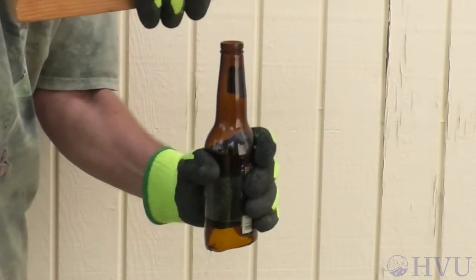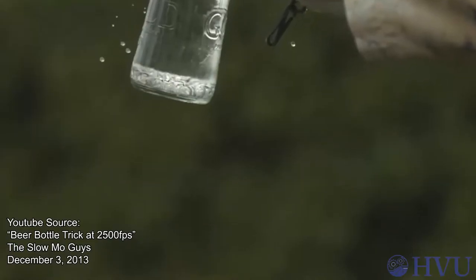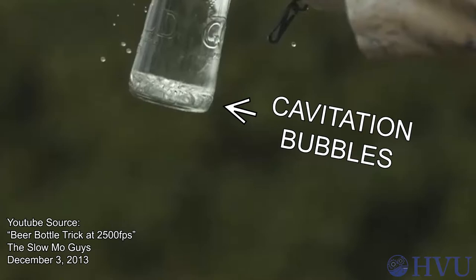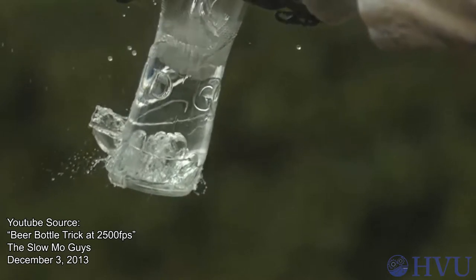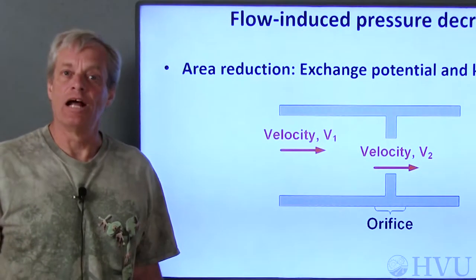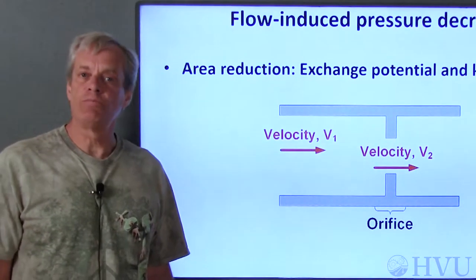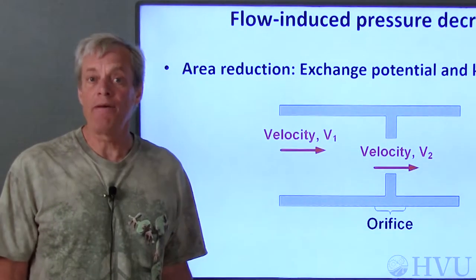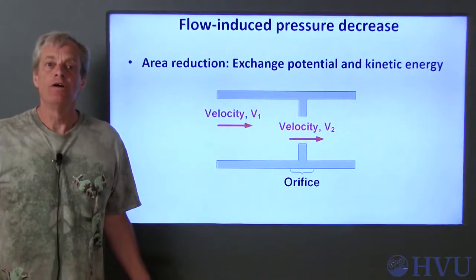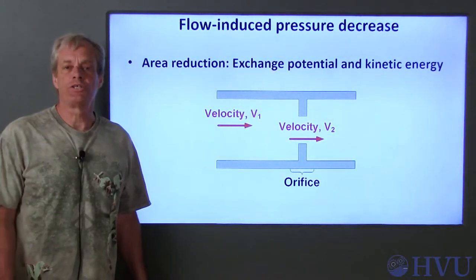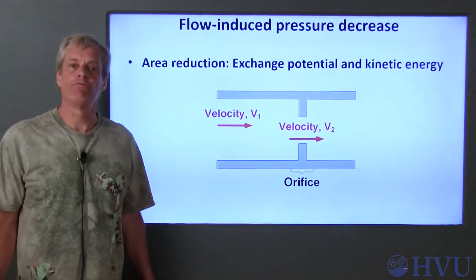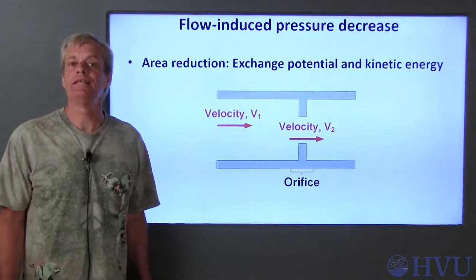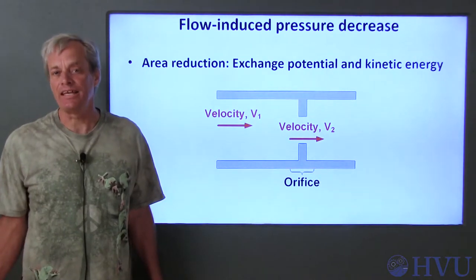If the cavitation bubbles are near or on a surface, these pressures can cause erosion and pitting of the surface. Now let's look at some flow phenomena that cause fluid pressures to drop and can lead to cavitation. Fluid pressure reflects the fluid's potential energy, while fluid flow velocity indicates kinetic energy.